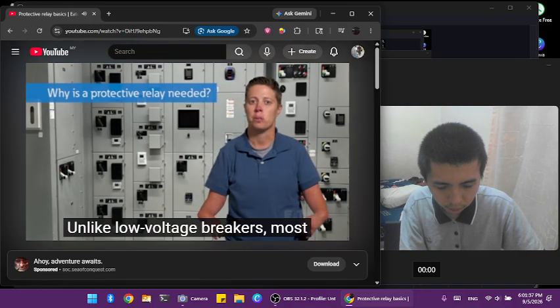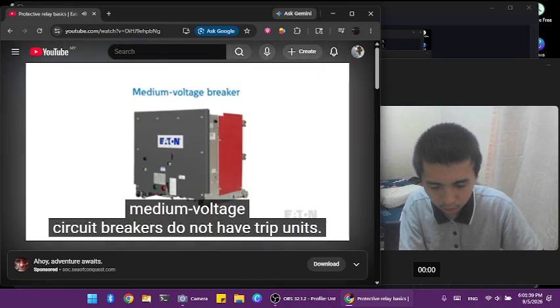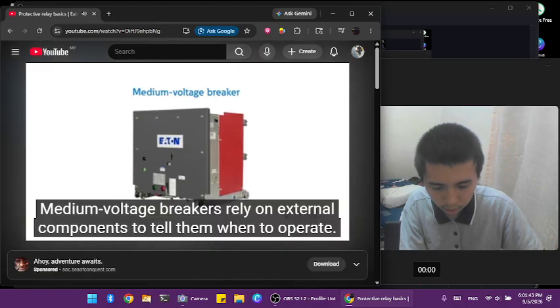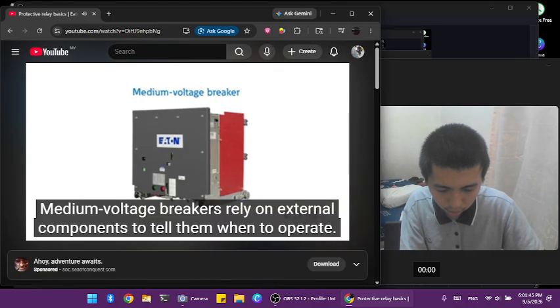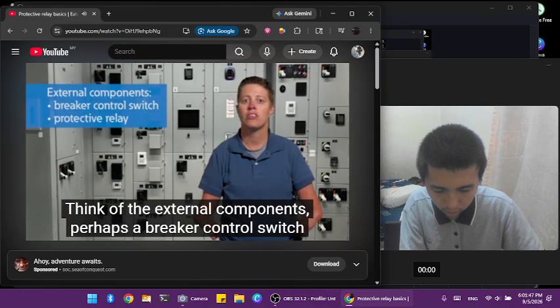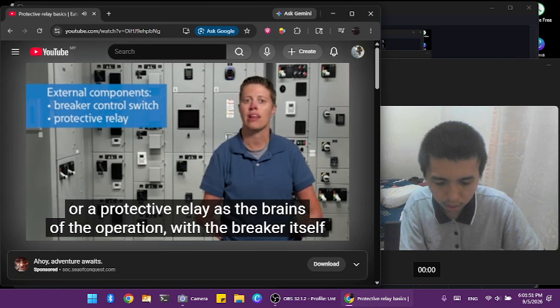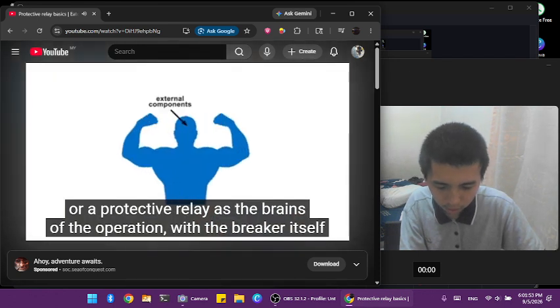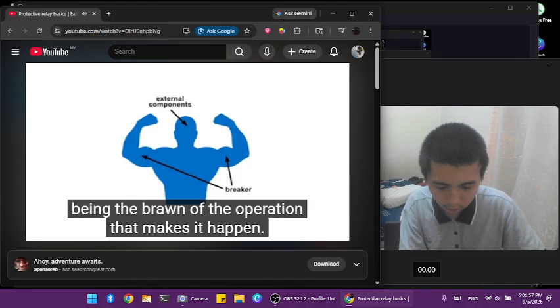Unlike low voltage breakers, most medium voltage circuit breakers do not have trip units. Medium voltage breakers rely on external components to tell them when to operate. Think of the external components, perhaps a breaker control switch or a protective relay, as the brains of the operation, with the breaker itself being the brawn of the operation that makes it happen.